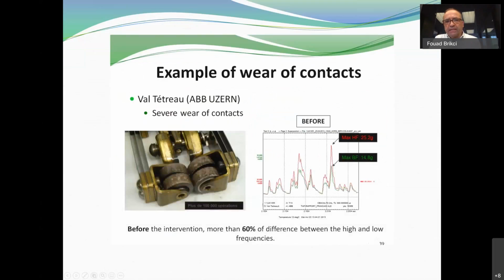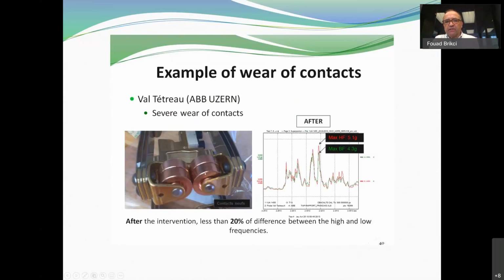Here we have some examples where we can see a worn contact against a new contact. On the vibration in red, you can see a missing impact, and with a new contact you can see in dark red that the impact is coming back. Another example of worn contacts: before the replacement, we have a 60% difference between the high and low frequency envelopes, and when we changed the contacts, you can see that we have less than 20% of difference between the high and low frequencies.